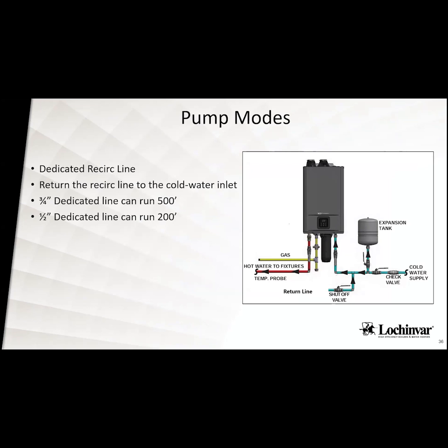So with a 3/4 inch line, the internal pump can go 500 feet. For a 1/2 inch line, it can run 200 feet. If you're doing a crossover tee, it's about 350 feet, because you've got half of that could be 1/2 inch, half of that could be 3/4. So you're about 350 feet with that crossover tee. And also make sure when you are recircing that you do have an expansion tank on the system, because we are recircing and we are going to have thermal expansion. And so we do need that expansion tank on those units.